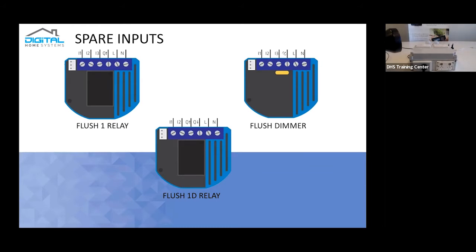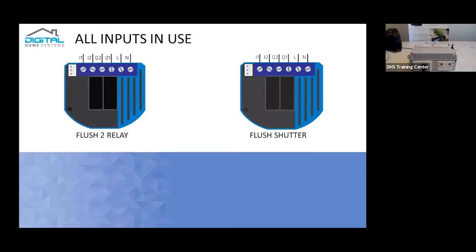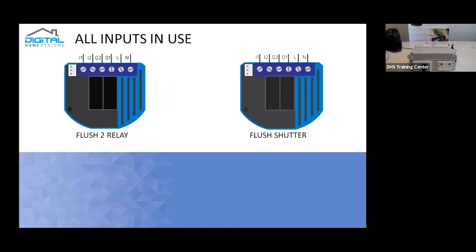Now, there are some devices which essentially have fewer relays that you can actually use. As a perfect example, the 1D relay only has one spare input. The reason for it is one of its actual inputs is replaced by an input for its actual dry contact. There are, of course, some devices that actually do not have inputs and all of them are already in use, such as the Flush 2 relay. Its I1 controls the Q1, its I2 controls the Q2, and the exact same thing for the Flush Shutter. Apart from instead of controlling a light, you specifically control a motor. This essentially goes the same with the Flush Shutter DC as well.